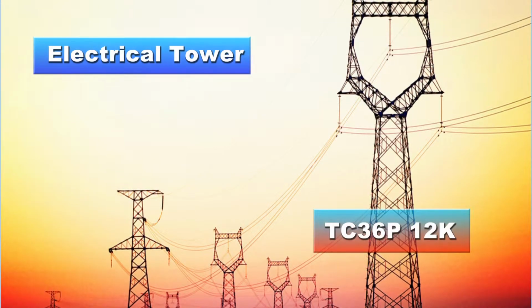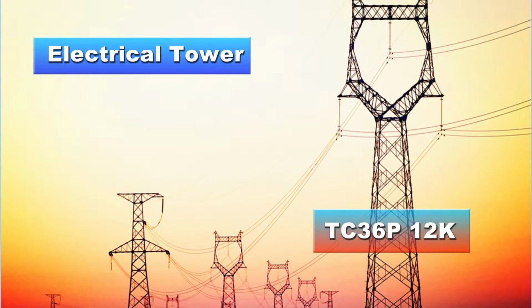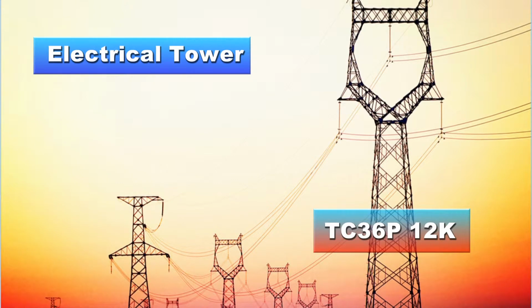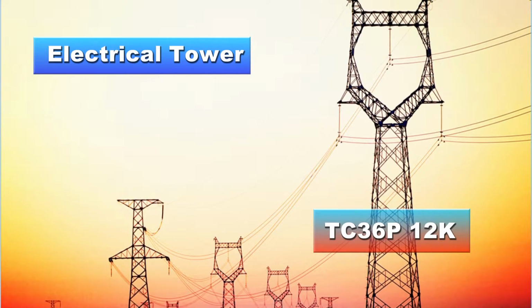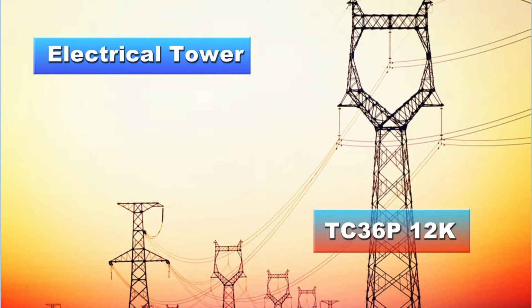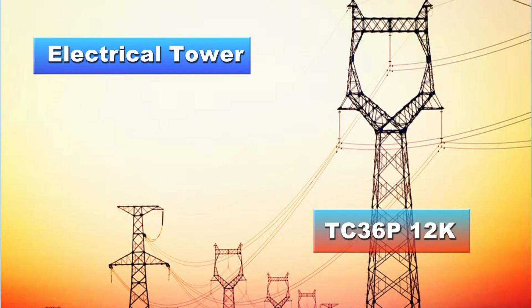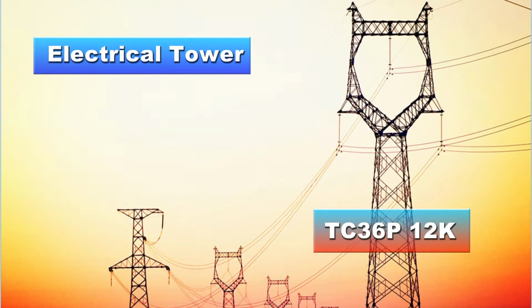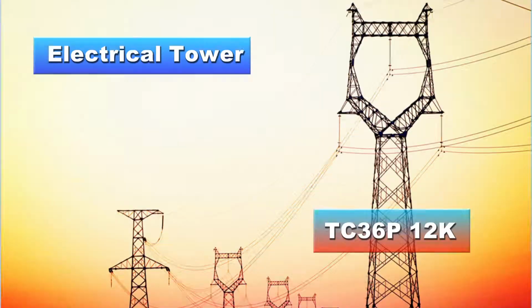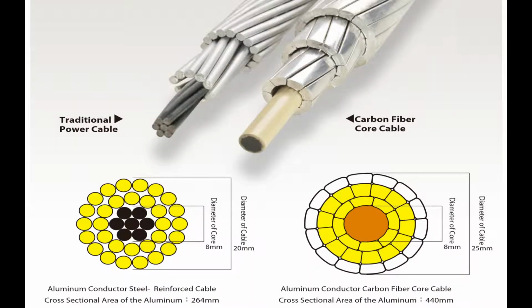By replacing steel core cables with composite core cables, the ACCC cable with FPC TC36P 12K carbon fiber can operate at a higher current level and push more power, doubling the current carrying capacity through the system without risk of sag and disruption of service.